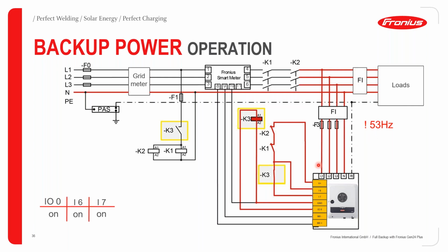In order to make sure that there isn't any negative feedback or overlap of power due to timing or transient failure, it is necessary to ensure that these disconnections and connections take place before power is supplied to the load via the batteries. So these are all safety measures taken by Fronius to ensure that there isn't any negative feedback and malfunction. So I believe I have addressed and answered the question that was put forward in this regard.